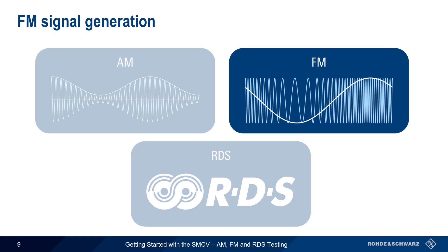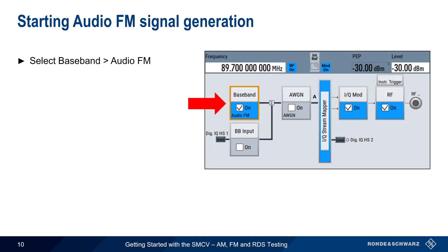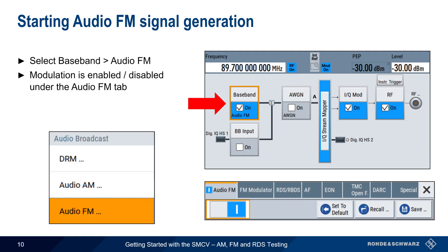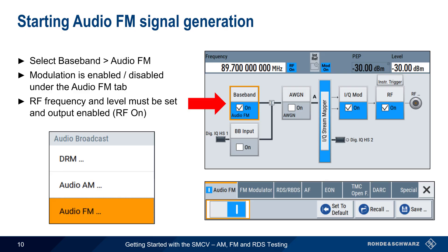Next, we'll look at configuring analog FM modulation, which is similar in many ways to how analog AM modulation is configured. As with AM, analog FM modulation is set by going to the Baseband block and selecting Audio FM from the menu. Modulation is enabled or disabled from the Audio FM tab. Remember that frequency and level must also be configured, and RF output must be enabled as well.